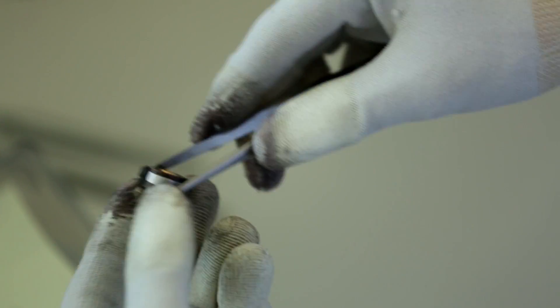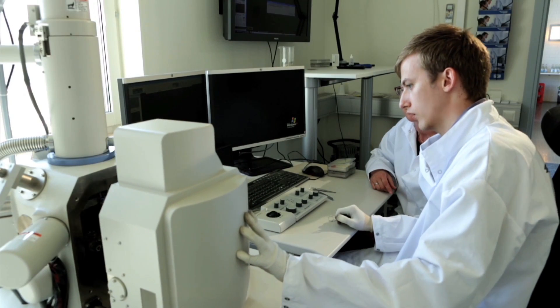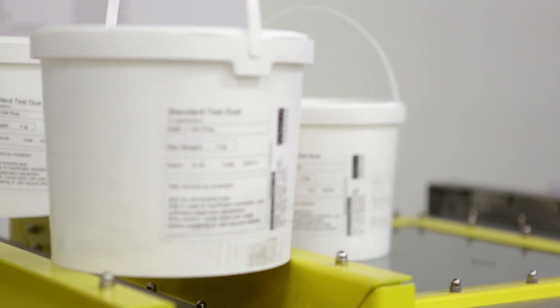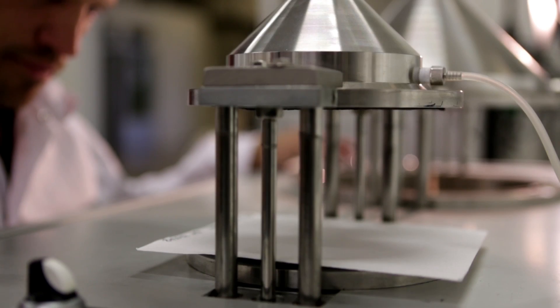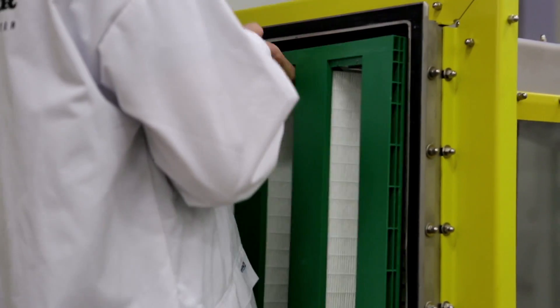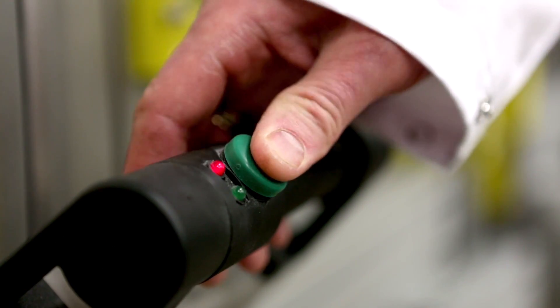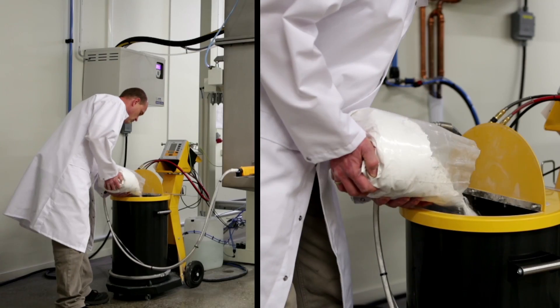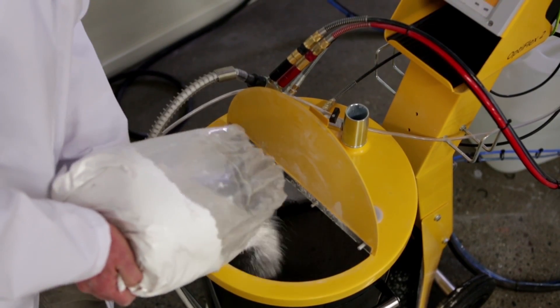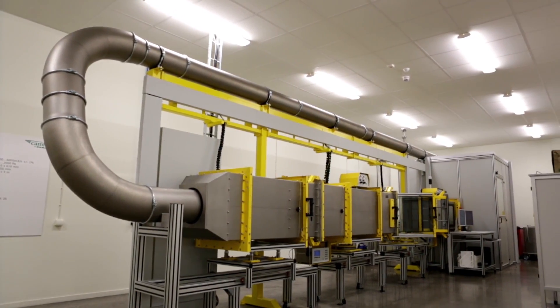Since our filters are built to meet turbine manufacturers' tough, stringent standards and are designed for use in the most challenging environments, nothing is left to chance. That's why we constructed our own test rig. The capacity of the test rig is impressive, with a flow rate up to 30,000 cubic meters per hour and maximum differential pressure of 12,000 Pascal. The filters are exposed to high dust loads, water, salt, and extreme pressure, because we know gas turbine filters in operation must never fail.